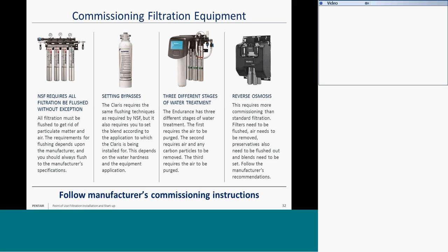Now, with reverse osmosis, there is more commissioning that is required. Of course, the filters need to be flushed and air needs to be removed, but also sometimes there's a preservative in the reverse osmosis cartridge that needs to be flushed out.